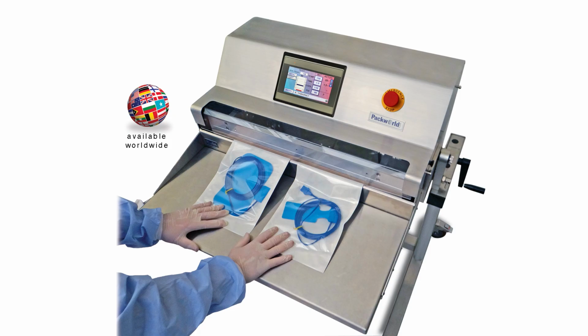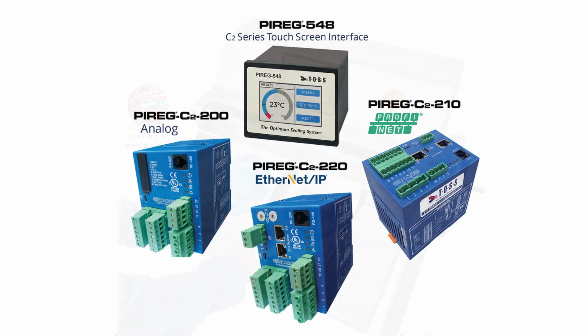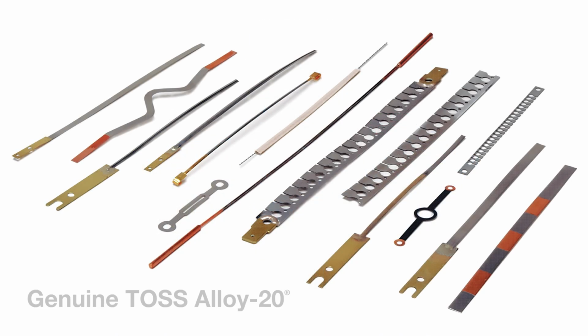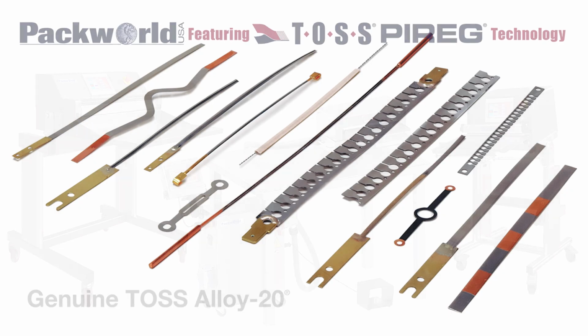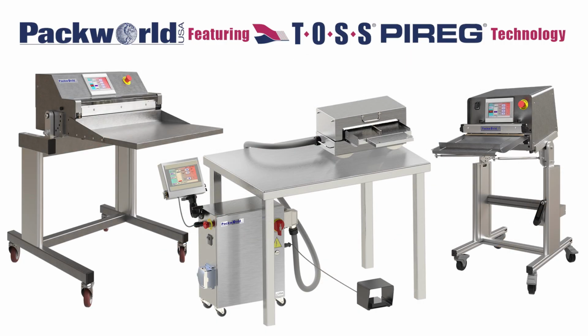The main concept making all of this possible is Ohm's law, which states resistance is equal to voltage divided by current. The PIREG controller uses Ohm's law to monitor and control the current and voltage to obtain a specific resistance. Because a known alloy, which we call alloy 20, is used to manufacture the heat seal bands and has a known resistance curve, a specific resistance can be calibrated to a specific temperature output and then accurately and repeatably produce that same temperature output.